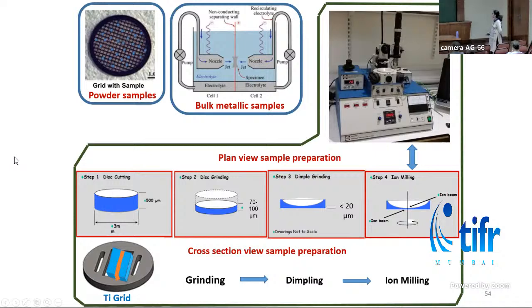TEM sample preparation is a very tedious job, and you can imagine at every stage we have to handle a sample which is 100 micron thick. So this really needs skill, and sample preparation can take as long as 3 to 4 days because the ion milling times depend on the sample, and they can be as long as 6 hours to 8 hours. So Jayesh does that job very sincerely for us. That's why we can get very good TEM samples.